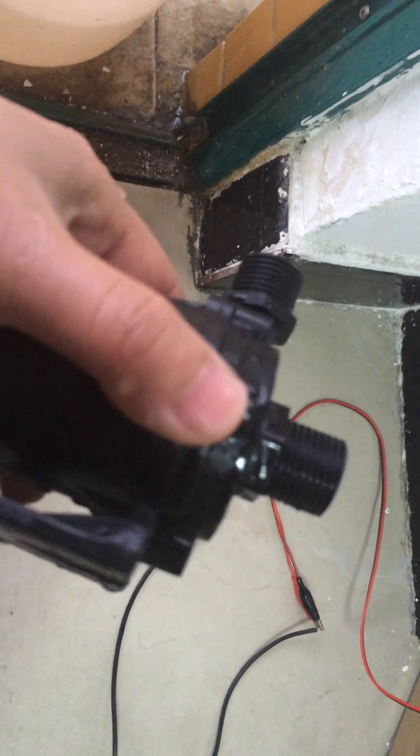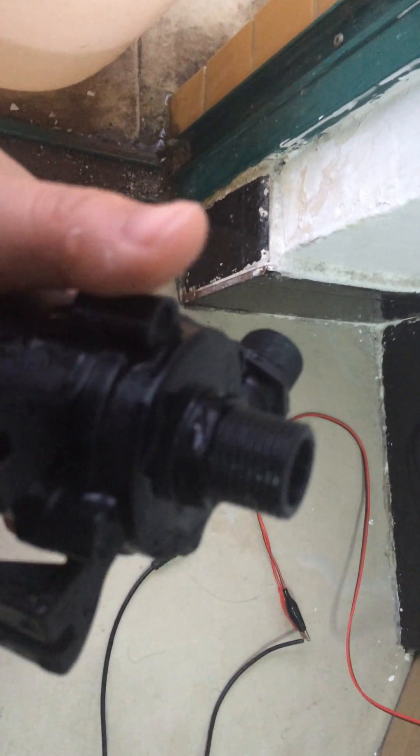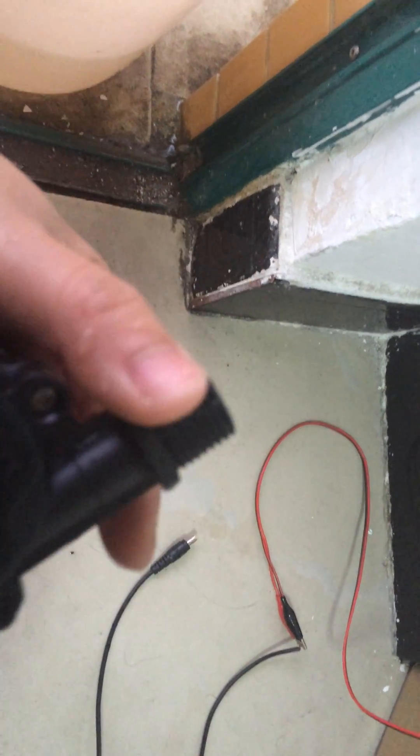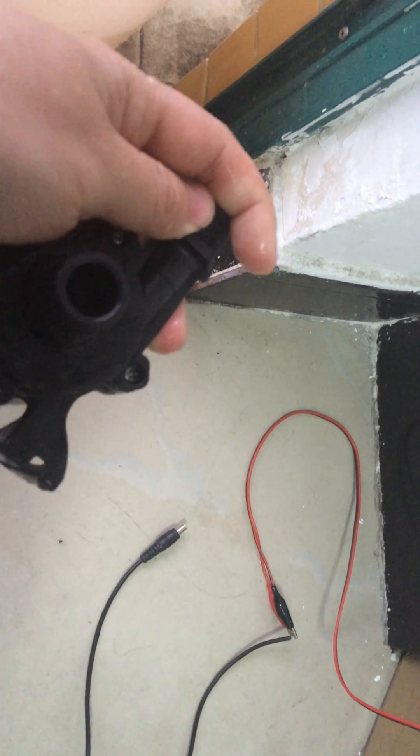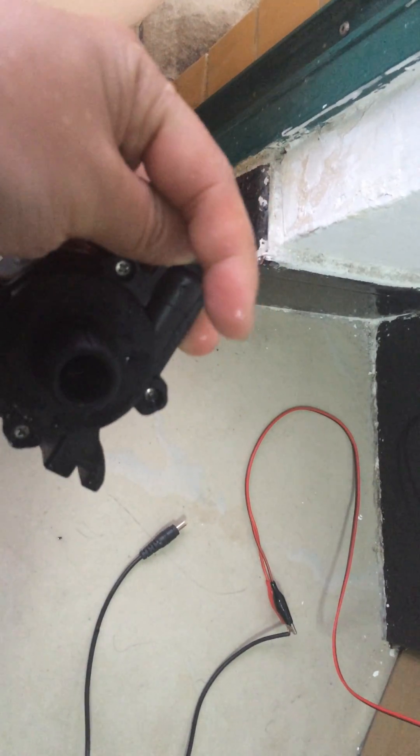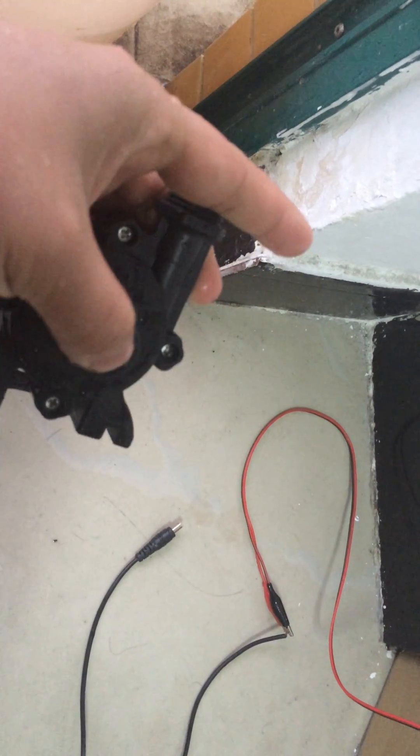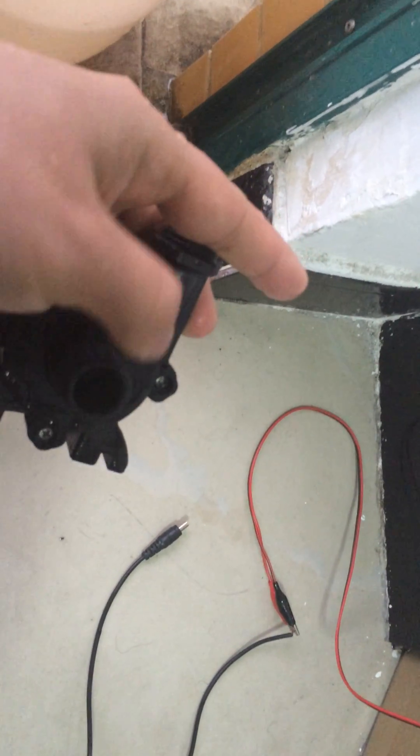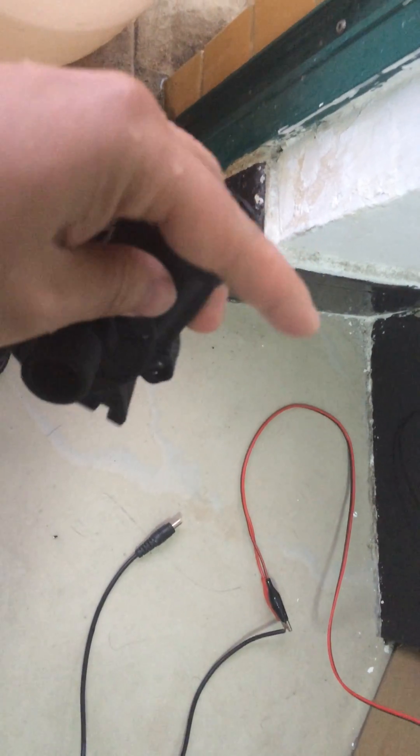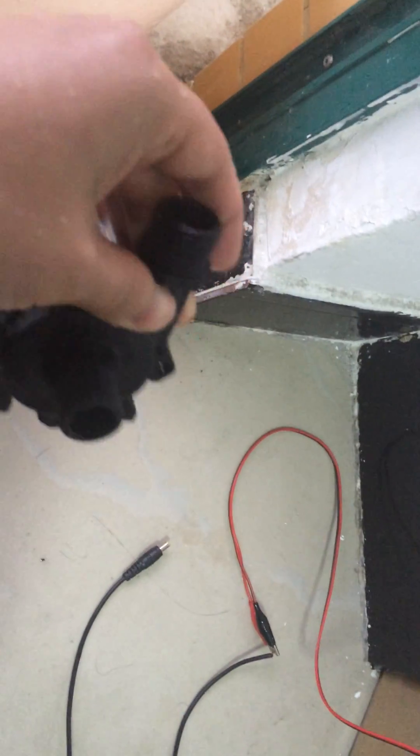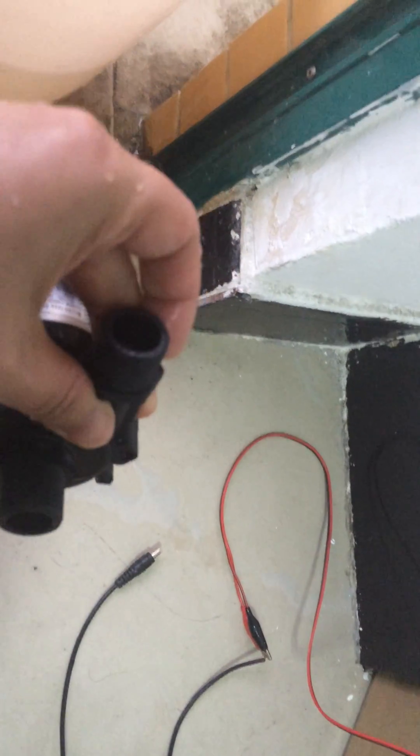But it is essential to make sure that there should be enough flow into inlet, because pump cannot be self-priming. It has no suction lift.